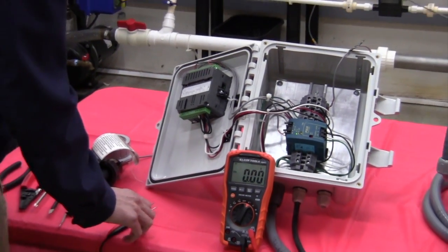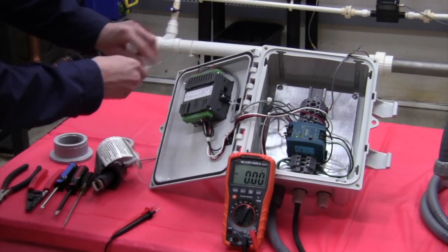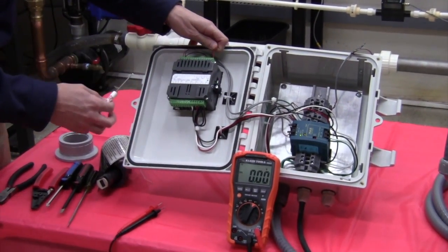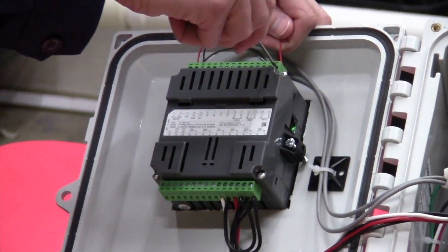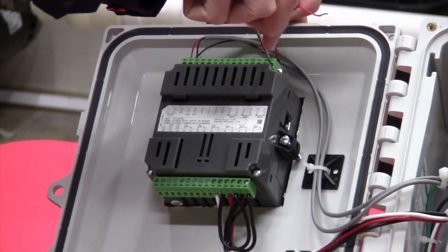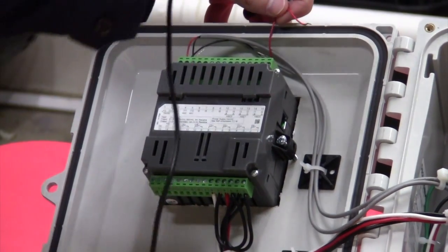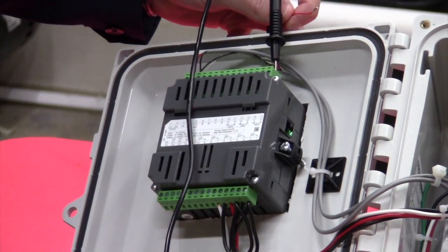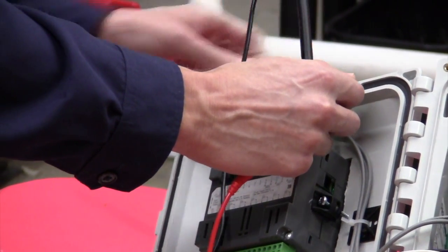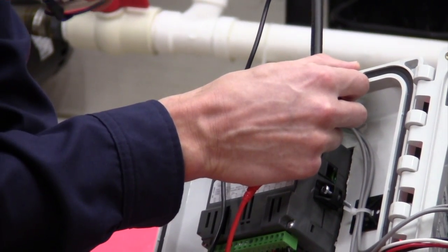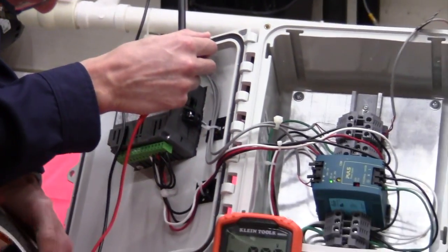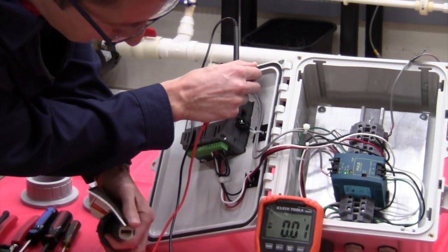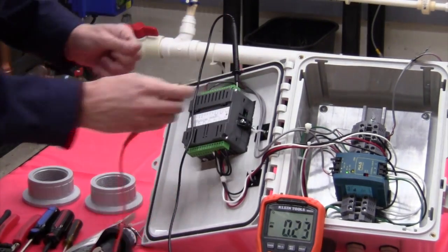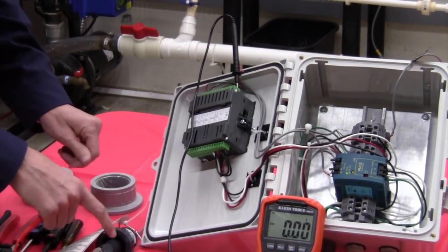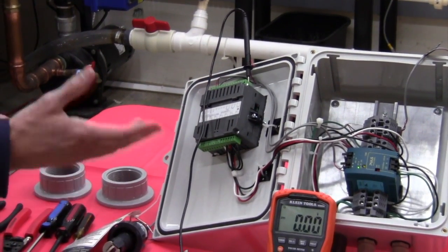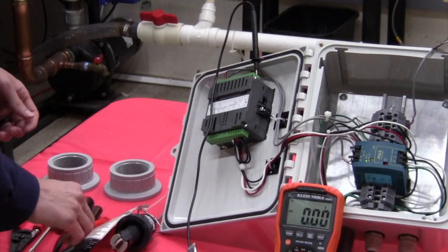The next step would be to take the red wire from my flow meter and take it off of terminal 15. Then I want to take the lead from my multimeter, stick it into terminal 15, take the other lead, put it on my red wire for the flow meter, and then if I give my paddle a spin, every time it spins, you should see that voltmeter jump up in voltage. Again, that is seeing a pulse every time one of these paddles passes by the sensor body. As long as you're doing that, you know the flow meter is outputting pulses properly.